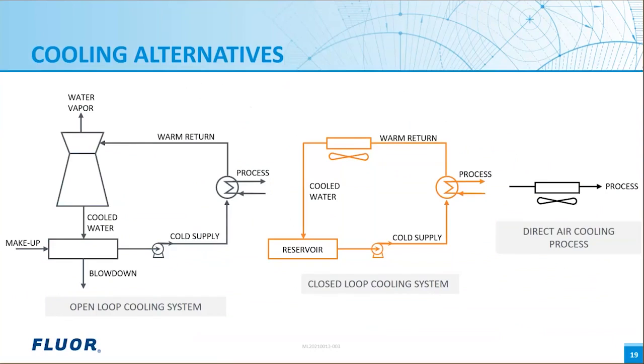The closed system, shown in the center, will not have water loss at all, the trade-off being usually a higher cooling medium supply temperature, higher power consumption, and potentially greater utility footprint for cooling. On this same diagram in the center, another variation would be to use an alternate water source, such as seawater, on the heat exchanger instead of air. The direct air cooling process on the right may have space constraints in process units, is not as efficient as water heat exchangers, and is limited to the approach to dry bulb temperature, but it is completely water-free.